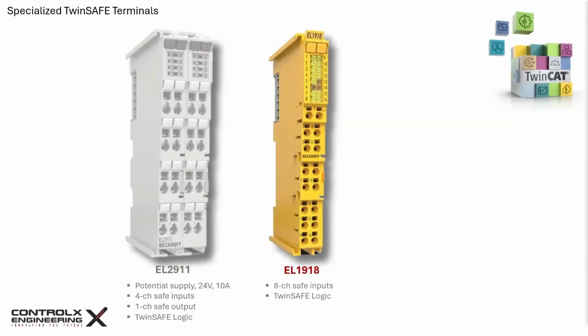Next, we have the EL1918, which is a TwinSAFE terminal with 8 fail-safe inputs for potential free contacts. This terminal also has integrated TwinSAFE logic functionality, similar to the EL6910. Thus, it can also be used as a safety controller. In the default state, the EL1918 is a simple input terminal whose input signals are transmitted via FSoE to a TwinSAFE logic-capable component. It also has a variant, the EL1918-2200, with 8 fail-safe inputs without TwinSAFE logic functionality, and is thus a pure input-only variant.